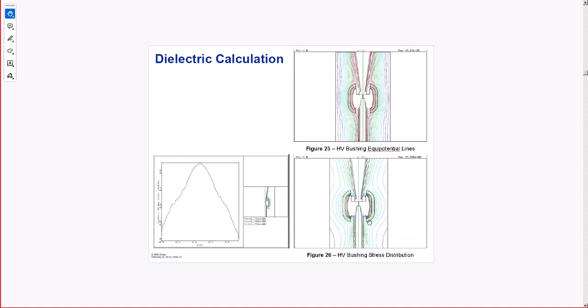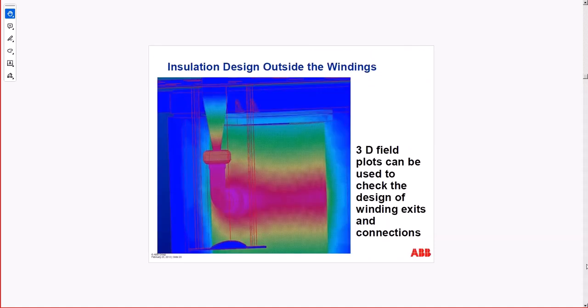What can be done? What can be done is the manufacturer or the designer should ask for a bushing size at 150%, and that will give you peace of mind. The bushings will not collapse easily being oversized. So that's a known method, but you know, price is another criterion these days, and sometimes they don't like that extra. But that's technically speaking the solution. And maintain the bushing, of course. You need to clean them and keep them clean. You cannot have debris, or the bushing can be destroyed by animals running across and being zapped by high voltage, and you know, it has happened in different places like Ottawa Power Station.